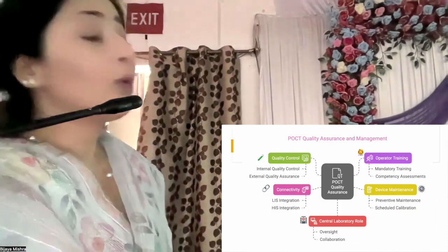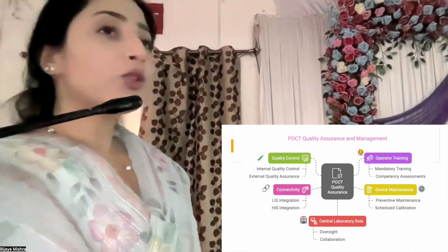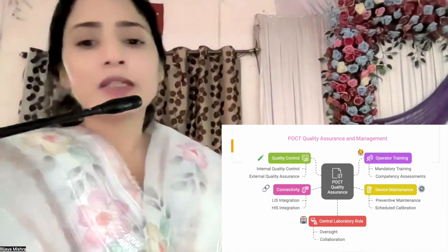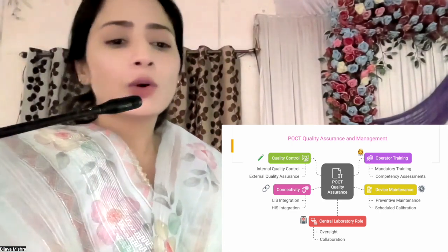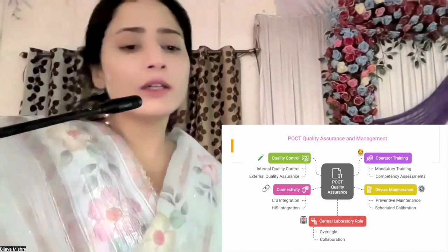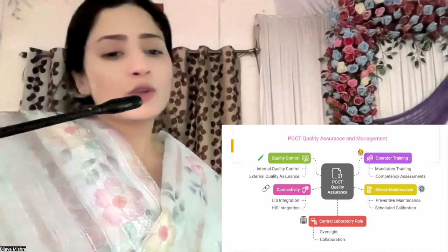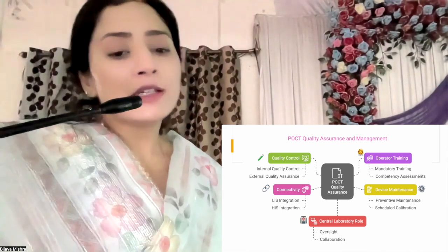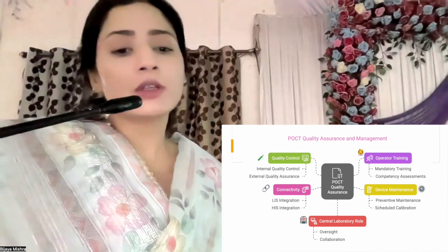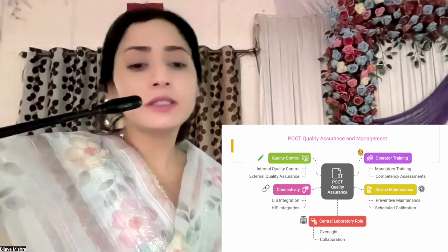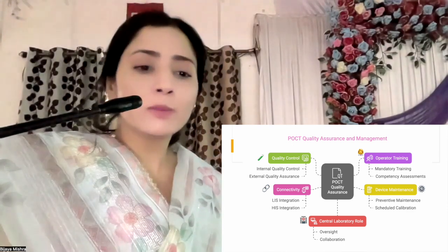When it comes to quality assurance, we want to make sure that the results given by the POCT device are accurate. Regular testing with control material is mandatory, and we should provide mandatory training to all persons running the POCT devices, and their competency should be assessed on a regular basis.